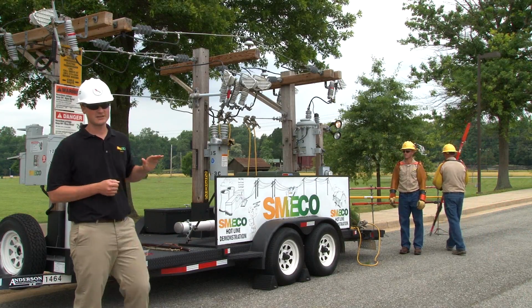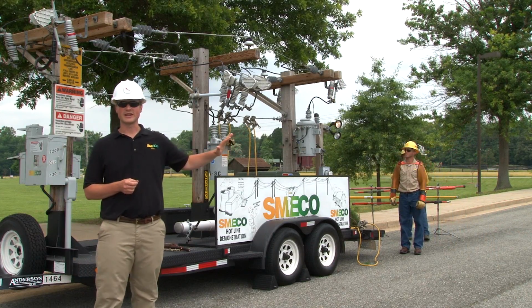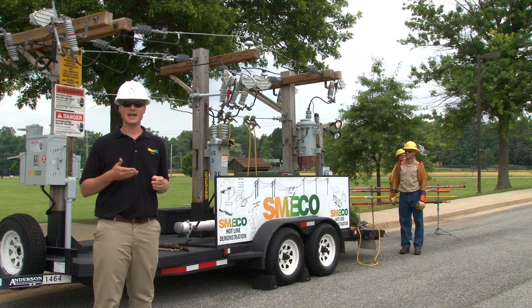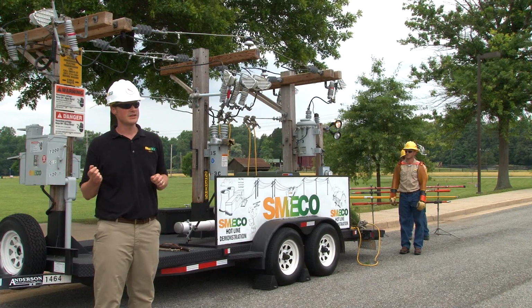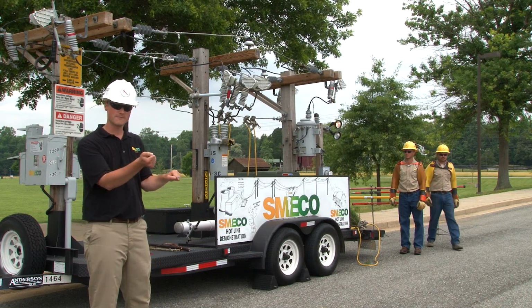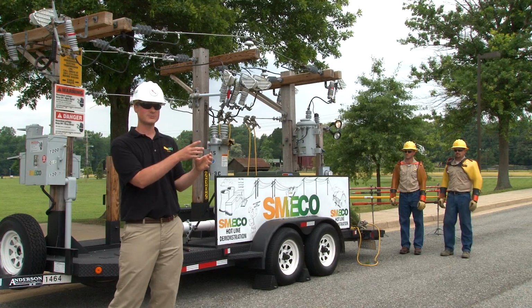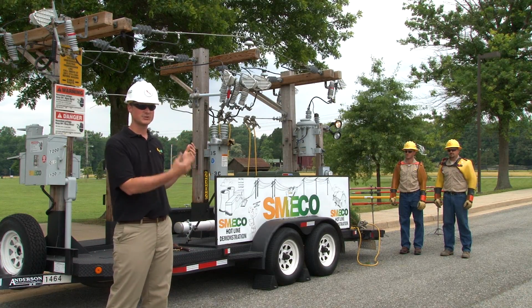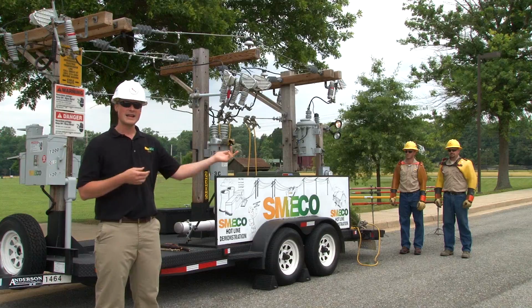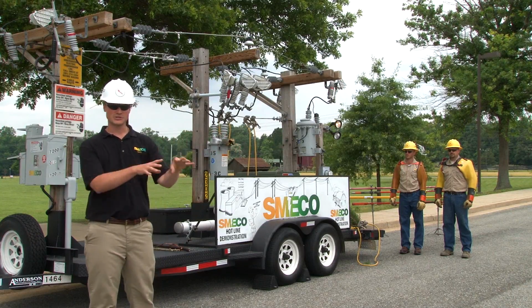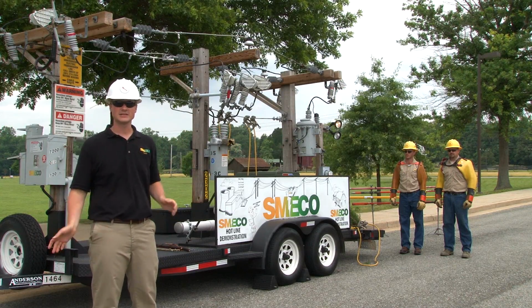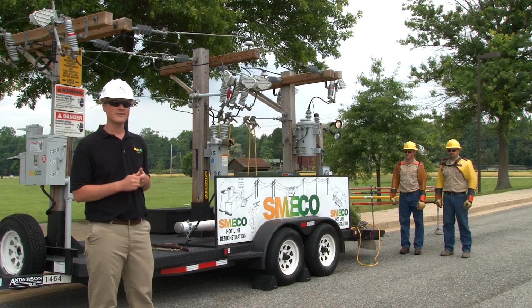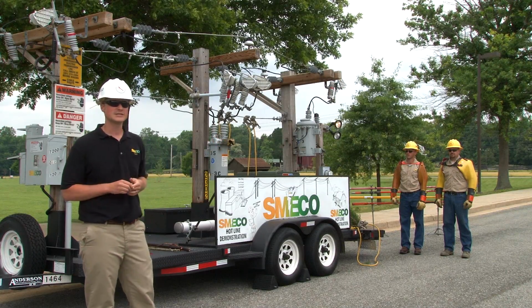Its easiest path to ground is in the center of that tree. So you can't necessarily just go up and do a touch test, and if you're still alive, think you can take it down. Because if you're using your chainsaw cutting through that tree, and you cut through that center root into the root ball, you just destroyed its easiest path to ground. Now that easiest path to ground is going to go from your chainsaw, through your body, through your feet, into the ground. So even if you went up and touched that tree and it seemed safe, that doesn't necessarily mean it's de-energized.